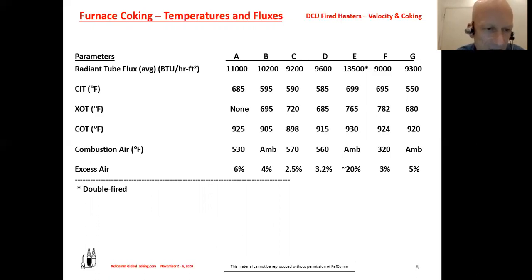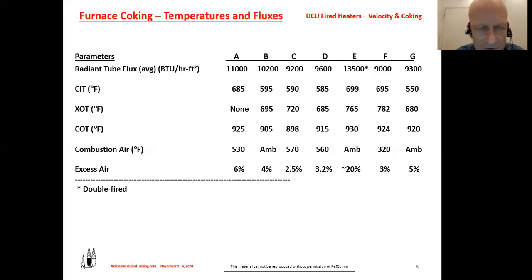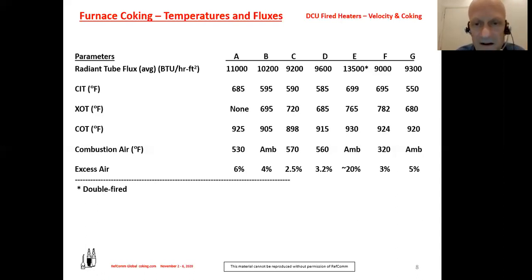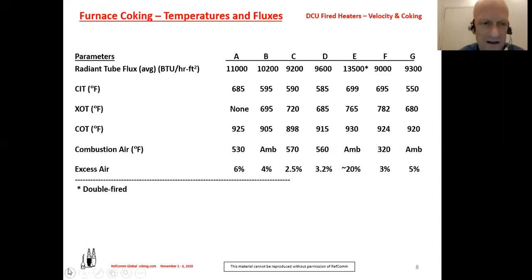Combustion air temperature and excess air show big variety across furnaces. Lower air temperature gives a cooler flame, radiating less heat, shifting heat from radiant to convection and lowering the coking rate. Increasing excess air brings in more nitrogen, giving a cooler flame, reducing radiant heat flux rate, shifting heat to the convection section, and slowing down coking rate. These are knobs you can play with to try to extend your furnace run before decoke.